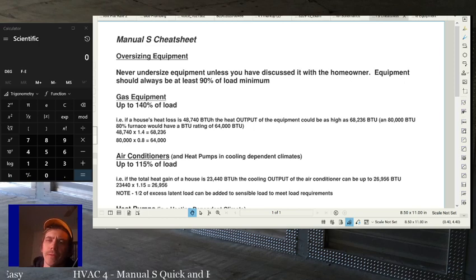First thing is you have to have already done a load calculation. You need to know the total heat required for the house based on design temperatures, the total amount of sensible cooling based on design temperatures, and the total amount of latent cooling needed based on design temperatures. Once you have that, you can go into selecting equipment.